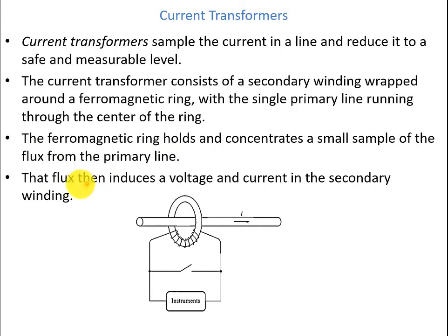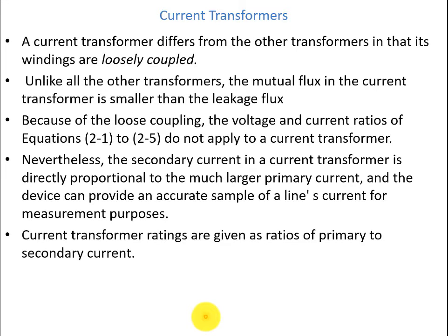That flux then induces a voltage and current in the secondary winding, so we can have the measurement by accordingly transforming that current to the actual value. A current transformer differs from other transformers in that its windings are loosely coupled.